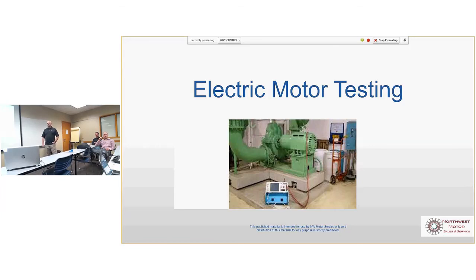Yeah. When you're testing, you want a hot motor, you don't want one that's been off for a while, ideally, to give you a better idea of what it's going to be like. Then again, a tester like this does a temperature compensation to 40 C, which is what he was talking about earlier. That's what the industry says motors should run at. So this tester will tell you what the megaohm reading would be if it was warm, which is kind of nice. But yeah, if you're just using a megger like what you guys have, you don't want it to be cold and sitting for days on end. That's the problem. But then again, if it's low, then that's what it's going to be when you hit the start button. So you've got to keep that in mind. So it is a real number.